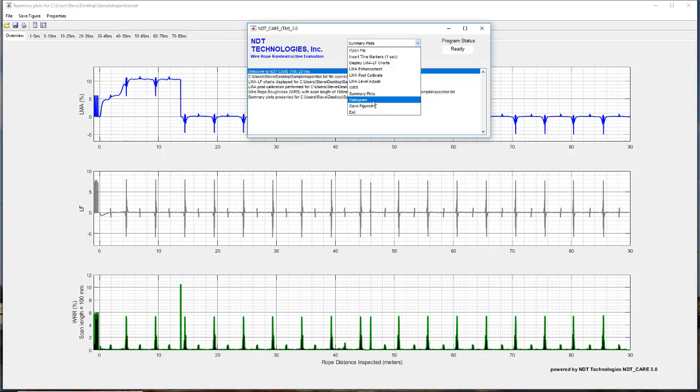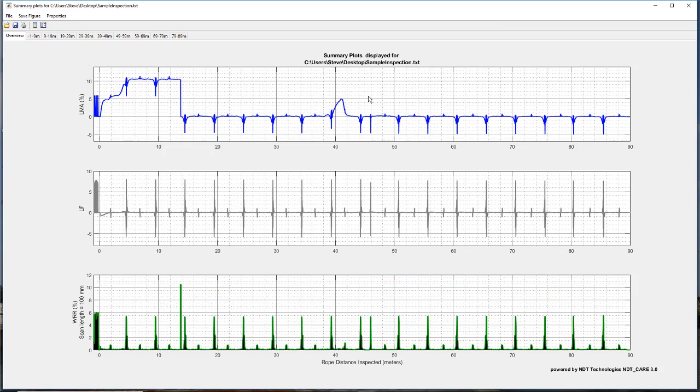Finally, we could look at our histogram function, and when we look at the histogram functions, it's really over the analysis that we have of interest. So our crosshairs appear, and I'm going to pick outside of this remagnetization effect and say maybe we're going to start the inspection here. So I only want to look at the histogram here, and then I'll go pretty close to the end right here.